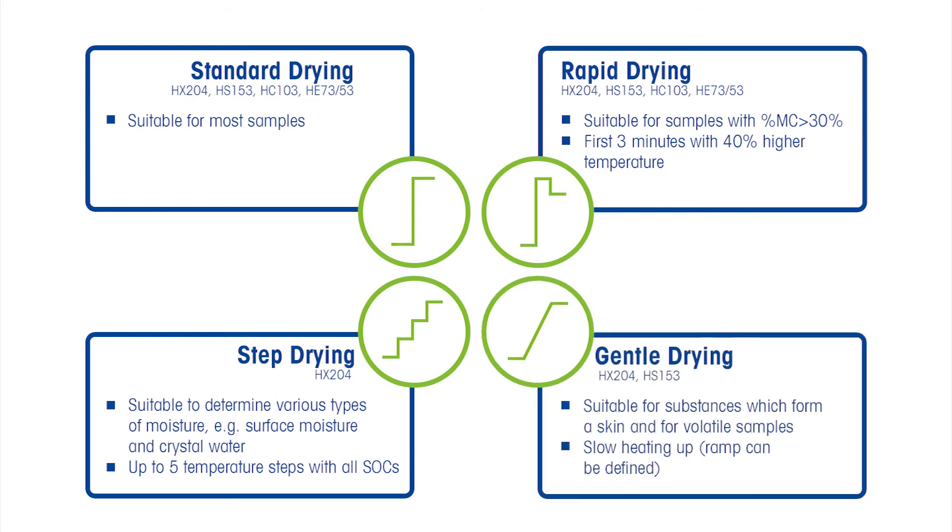Rapid drying is good for samples with moisture content higher than 30%. Step drying can be used to differentiate between surface and bound moisture. And gentle drying for skin-forming or temperature-sensitive samples.